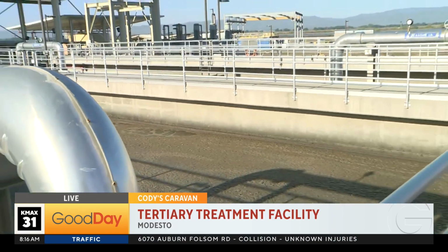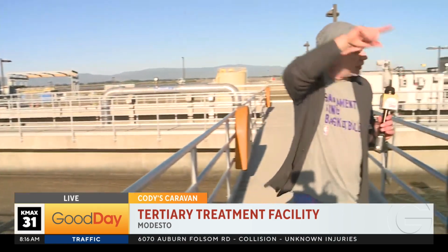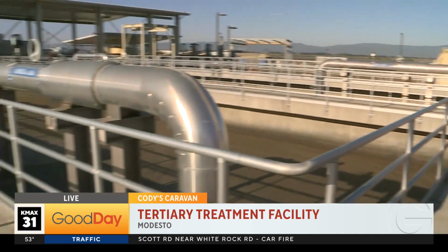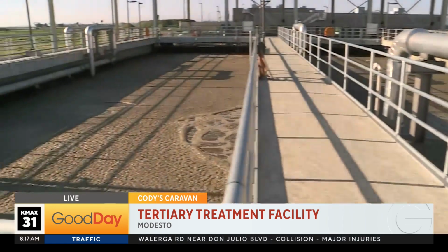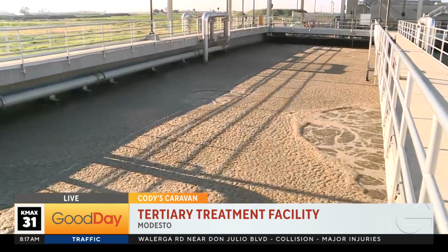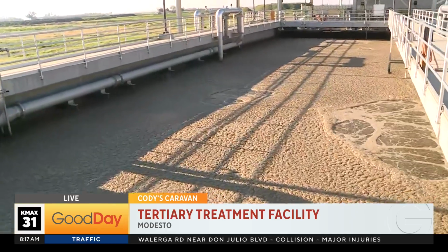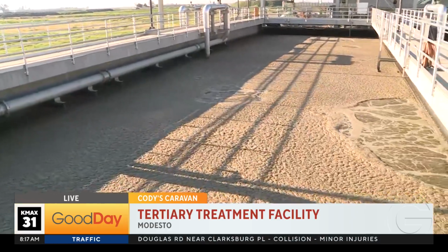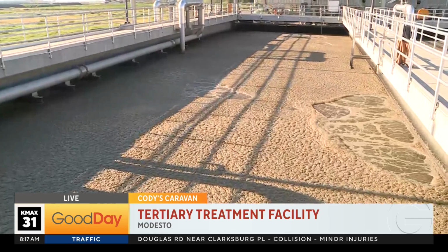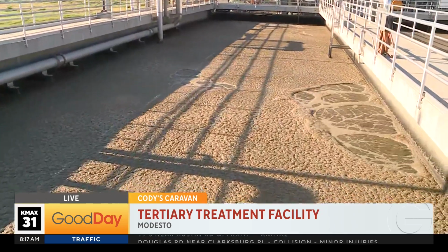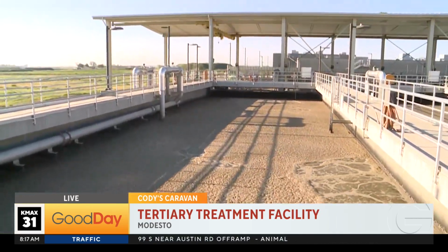So it basically takes like a four-time lap, basically? Yeah, so this particular plant will recycle these microbes around roughly 4 times or so with the water so that they get enough passes through the deoxygenation and the reoxygenation. Make sure we get all those ammonia and nitrate levels down before they pass through the filters and onto the disinfection process. Because if you let that stuff naturally just go back into the waterways, then you're going to get algae blooms and all sorts of crazy stuff.